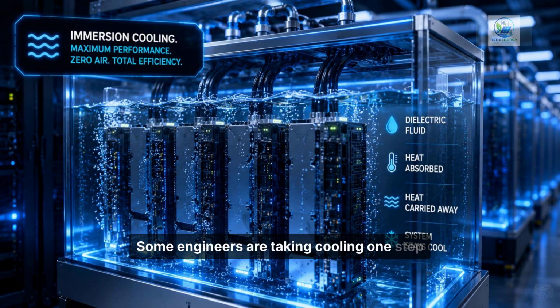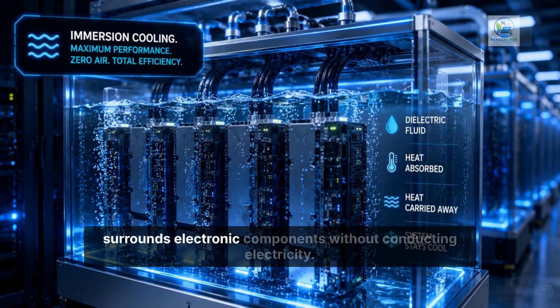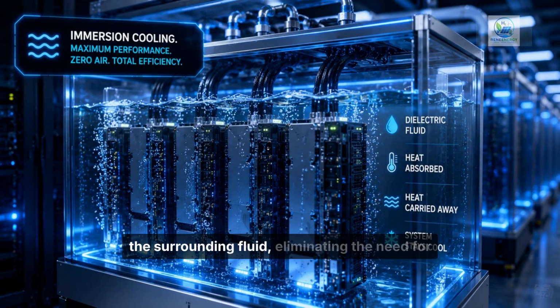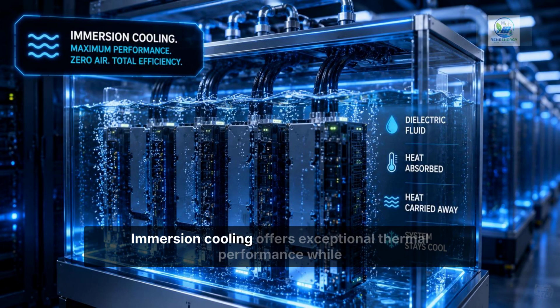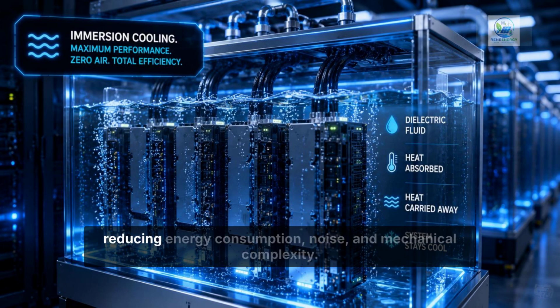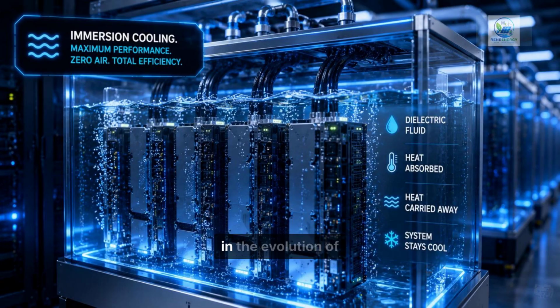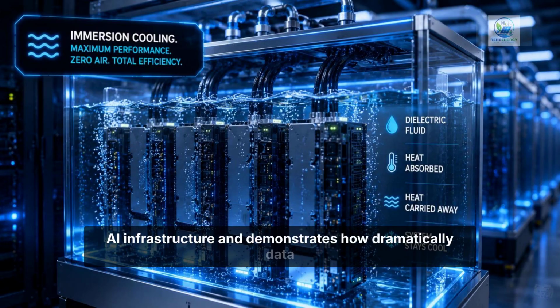Some engineers are taking cooling one step further. Rather than circulating liquid through cold plates, entire servers are submerged inside specially designed tanks filled with dielectric fluid, a liquid that safely surrounds electronic components without conducting electricity. Heat moves directly from the processors into the surrounding fluid, eliminating the need for many traditional fans and airflow systems. The warmed liquid is then circulated through external heat exchangers, where it is cooled before returning to the tank. Immersion cooling offers exceptional thermal performance while reducing energy consumption, noise, and mechanical complexity. It represents one of the boldest innovations in the evolution of AI infrastructure and demonstrates how dramatically data center design is changing.